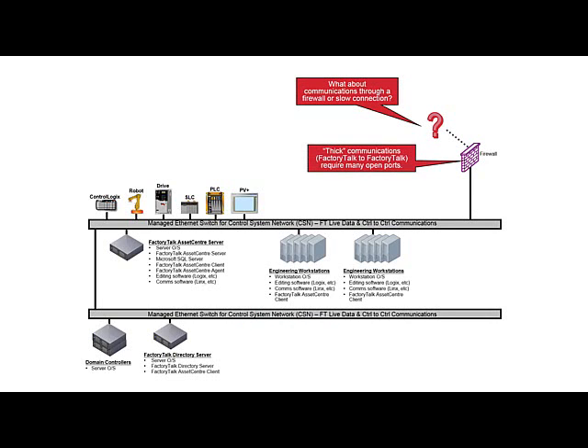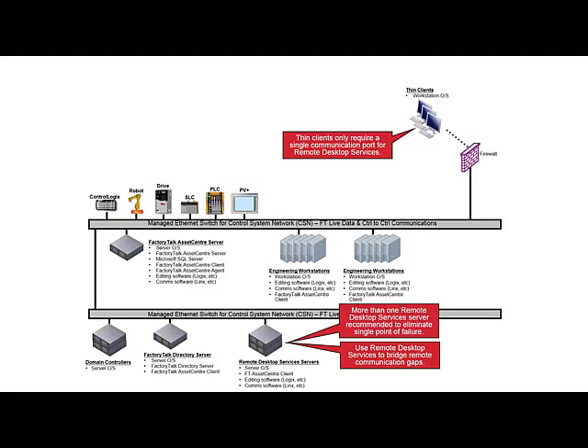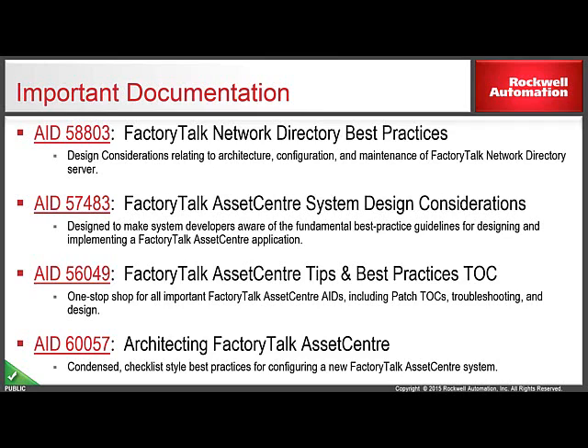Finally, some architectures require remote connections, either through a firewall or over a network connection that is unreliable or slow. For these architectures, a direct connection from the FactoryTalk Asset Center client to its server is rarely desirable. Instead, use Microsoft Remote Desktop Services to bridge this communications gap. Remote Desktop Services allows remote users to log into a server and create a new instance of a client, all without having the software installed on the client itself. When using Remote Desktop Services, it is recommended to use at least two server hosts for the purposes of high availability. For more information on designing FactoryTalk Asset Center systems, please refer to the resources located on the Rockwell Automation Knowledge Base.